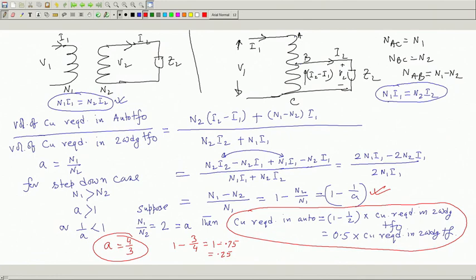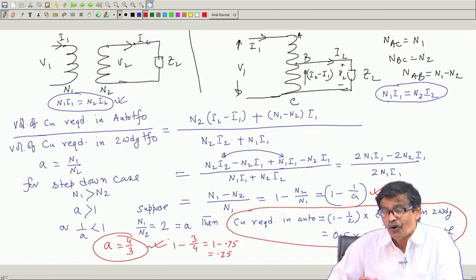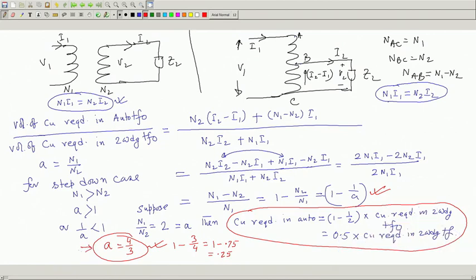Savings of copper will be more as A approaches 1. If you decrease the value of A, savings will still happen, but not at as high a rate as when A equals 4 by 3. So we understand that in an auto transformer, savings of copper will always take place, whether more or less depending on the ratio. As A approaches 1, savings of copper become greater, and lesser copper is required.